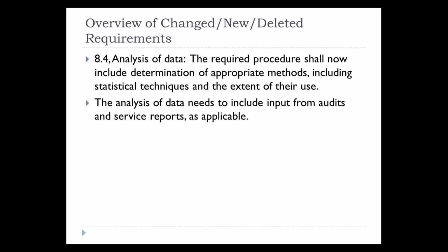8.4, analysis of data. The required procedure shall now include determination of appropriate methods, including statistical techniques and the extent of their use. So again, there was always a procedural requirement defining now determination of appropriate methods, including statistical techniques and the extent of their use. The analysis of data needs to include input from audits and service reports as applicable.